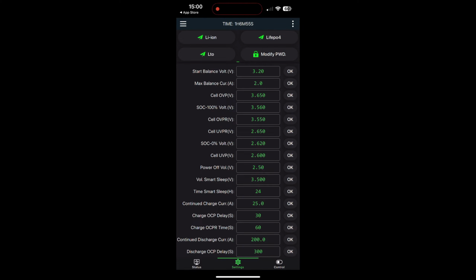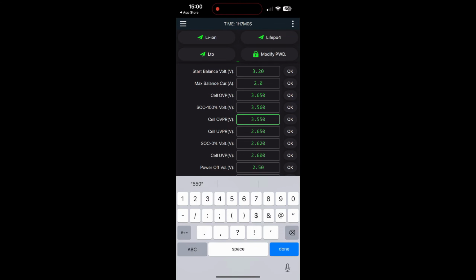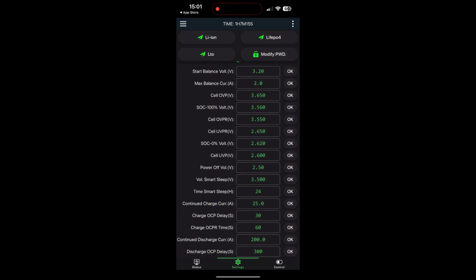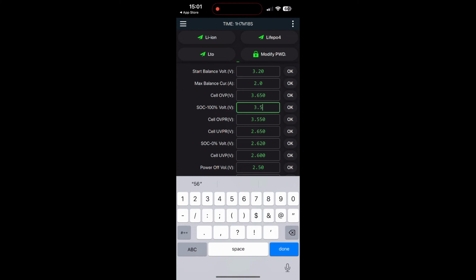All right. Now, I'm going to jump a setting, and I'm going to go to cell OVPR, which stands for over voltage protection reset. We'll still leave it at 3.55. Above there, all right, is SOC, which stands for state of charge, 100% volt. Now, what this basically means is that you can set at what point you want your battery bank to state that it's at 100% of the usable capacity, not total capacity, usable capacity.